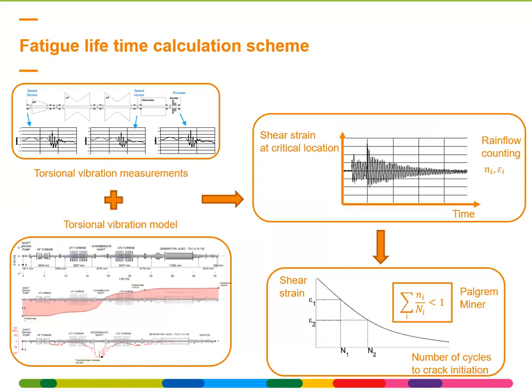You have, of course, the endurance limit. So if you have very low torsional vibration amplitudes, you could have an infinite life because you're not accumulating fatigue damage. Once you go beyond the endurance limit, you will start accumulating fatigue damage and you will reach at a certain moment in time crack initiation if the amplitudes are large enough. So any assessment of how critical your torsional vibrations are should be based on fatigue lifetime considerations. And this is what is shown here on this slide. This is how you should calculate the fatigue lifetime and how you should assess the criticality.